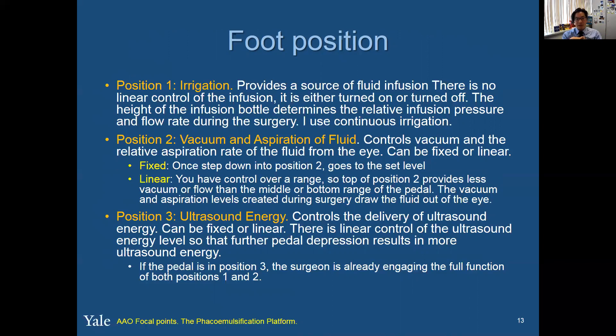Foot position one on the foot pedals of a phaco machine is set at irrigation, and that provides a source of fluid infusion. I basically use continuous irrigation for all my cases because I don't want to have to think about stepping down into foot position one for 10% to 15% of the entire time I'm in the eye. Of course, if you hit a complication, you just kick the foot pedal to turn the irrigation on or off. Foot position two is the vacuum and aspiration of fluid — it controls the vacuum and relative aspiration rate. That can be set at fixed or linear, and you just look at that line. If it's fixed, once you step down into position two, it goes straight to that set level.